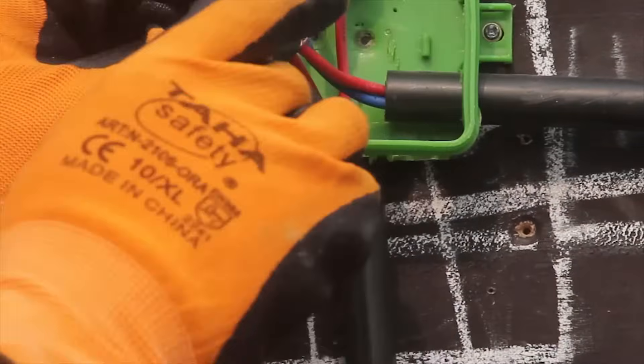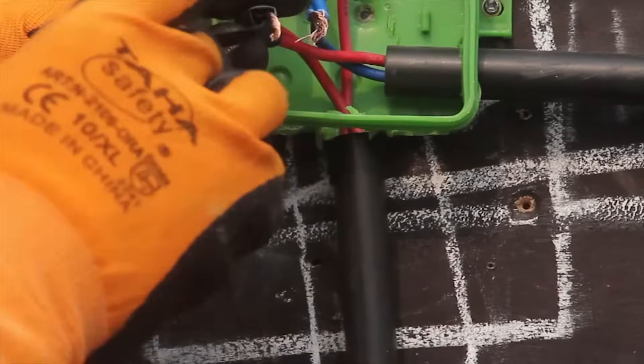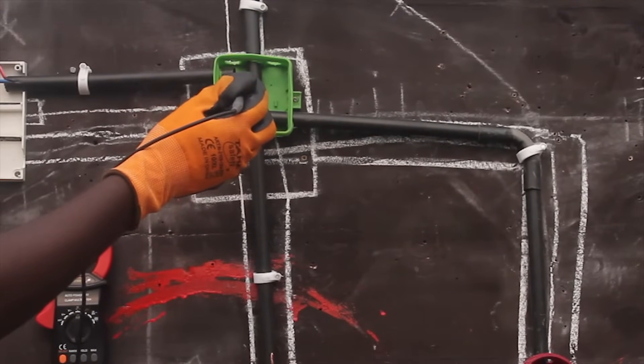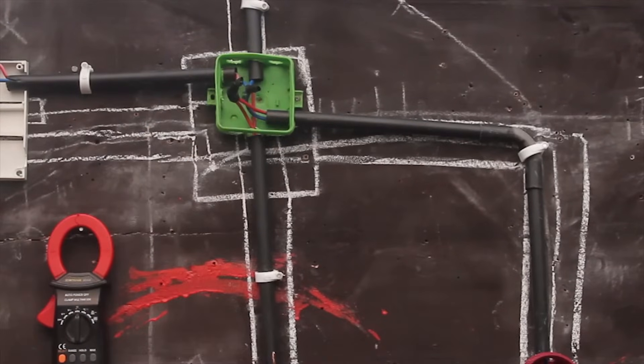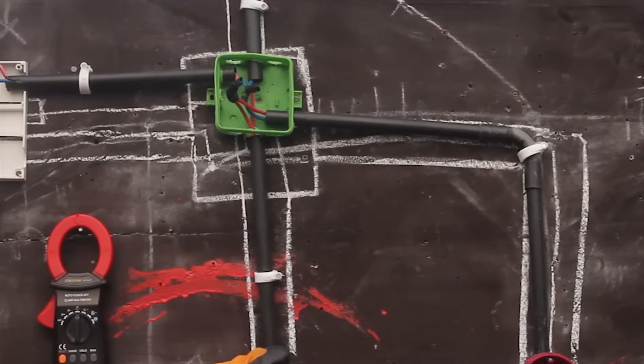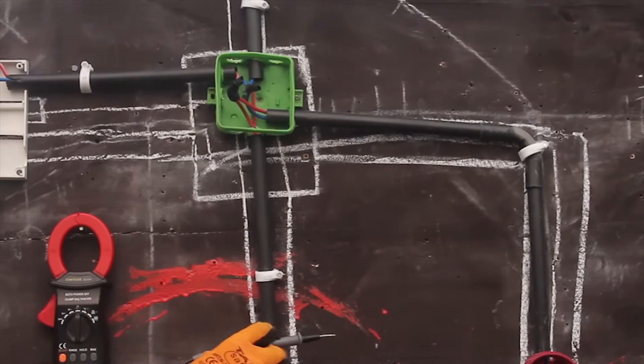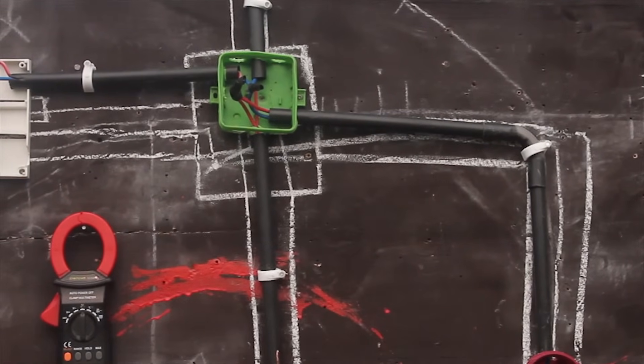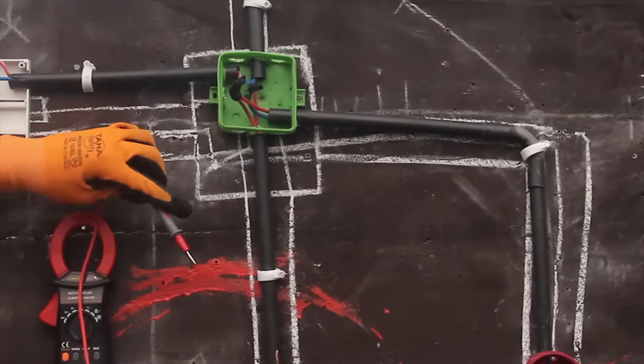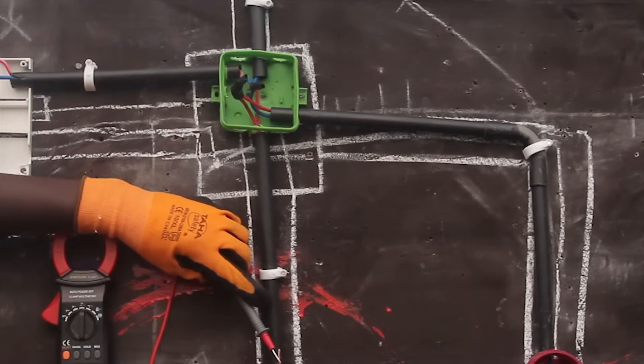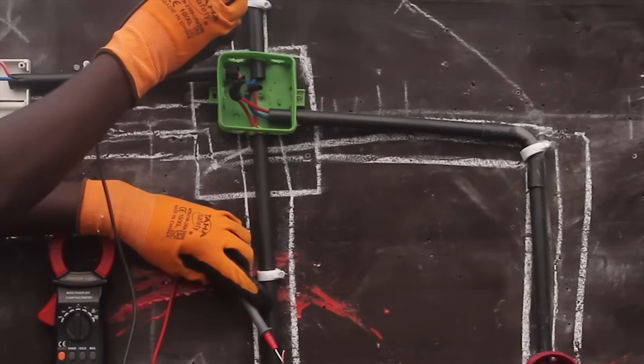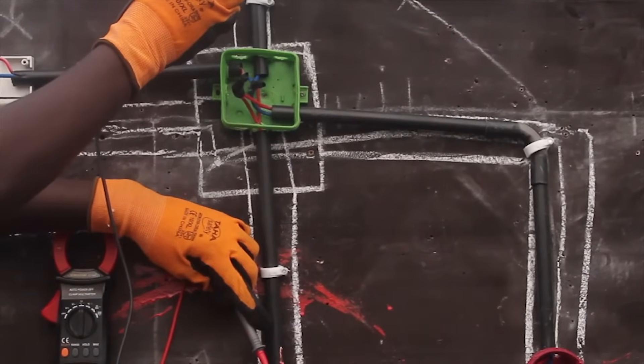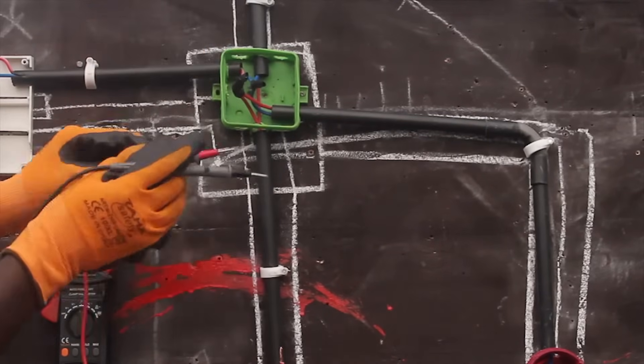After that, using the clamp meter or digital multimeter, we are going to measure the continuity of each connection — for example, the neutral cable to the lamp, and the neutral cable from the fuse to the junction box. For each connection you must do a continuity test in order to make sure that the junctions you made are done correctly.